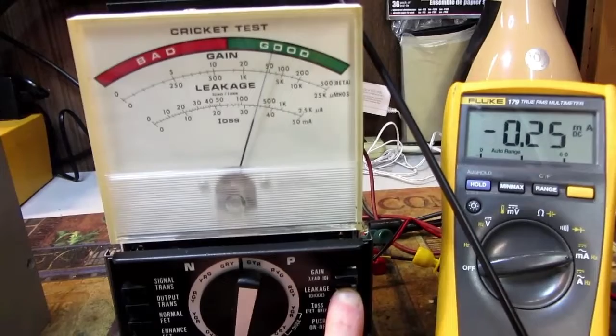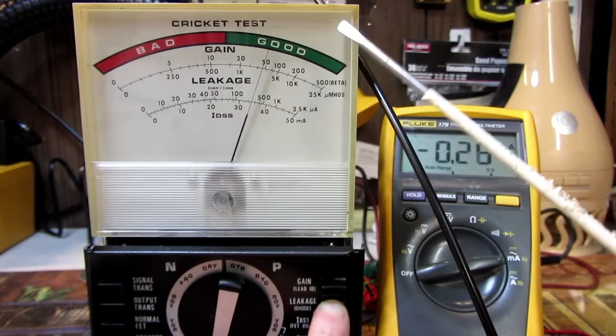As you'll see, this is 100 microamps. The next line here is 200, the next line is 300. So you're going to be right between the two here, and as you see, this is the microamp range, and this right here would have been 2500 microamps. So we have this calibrated. Next, you have to go back and repeat the first step, and you need to go back and forth until both of these are calibrated correctly.